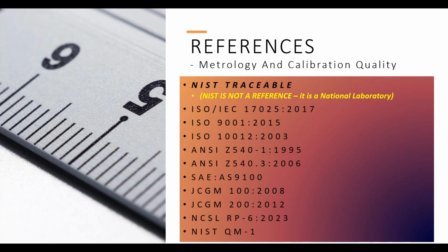Then you have your ANSI Z540s. These are how you report data to your customers. You got SAE AS9100, which is an aerospace document about how different aspects of the materials and the calibration all work together for safety, including foreign object debris inside the equipment.